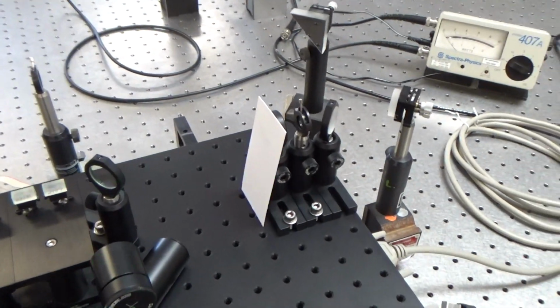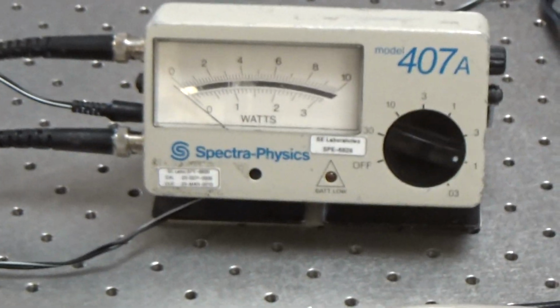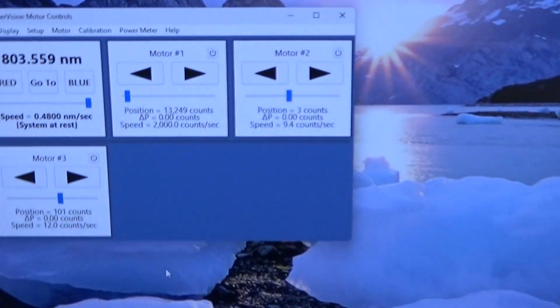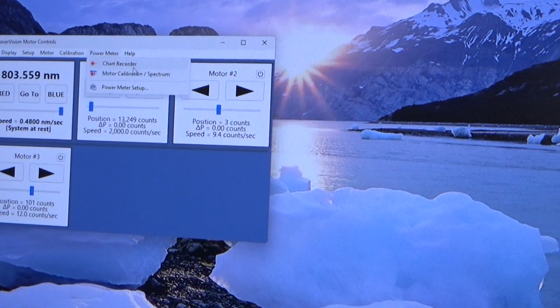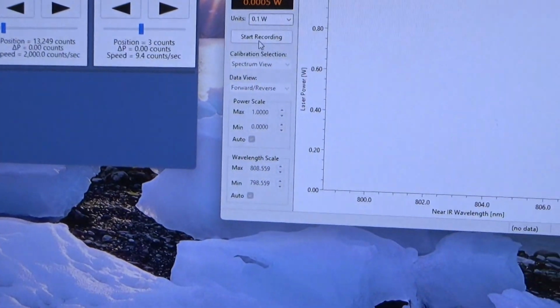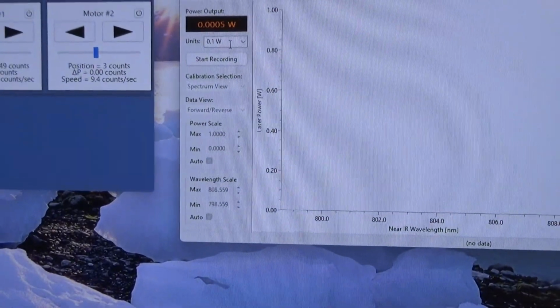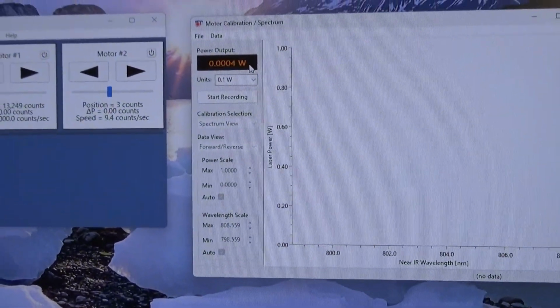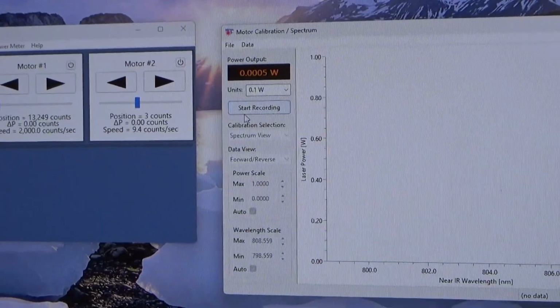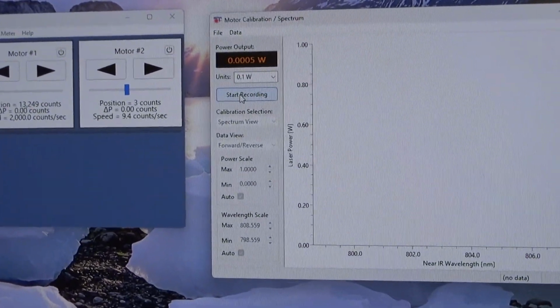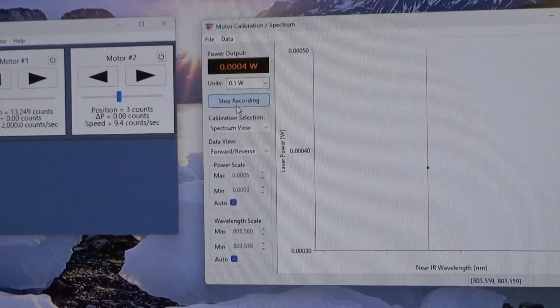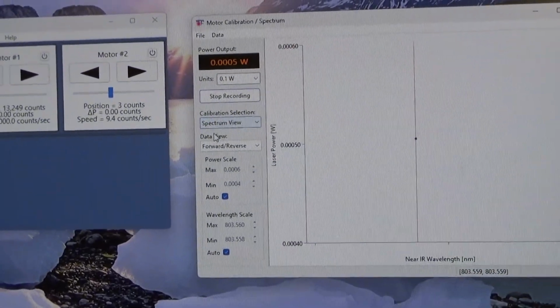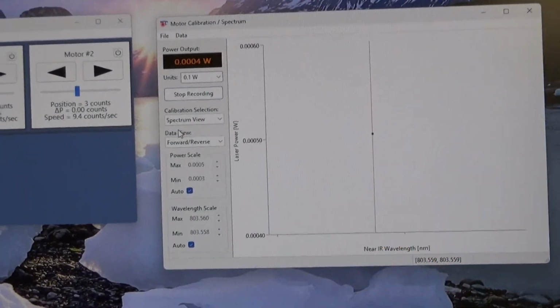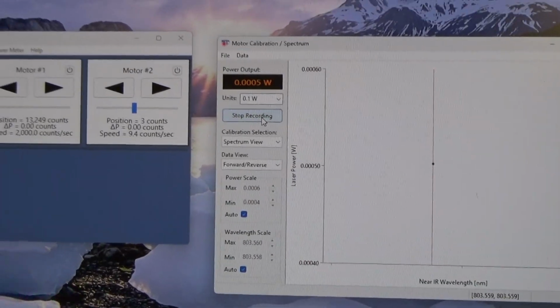Now, I'll take that time. I've got the beam to the power meter block, and so I can set the 0, go into the power meter function here, and you can see I've got the correct unit scale here, and we're very nearly 0, so I'm not going to adjust that. I can start recording at any time. It's collecting data, but nothing is happening because the near-infrared wavelength's not changing.